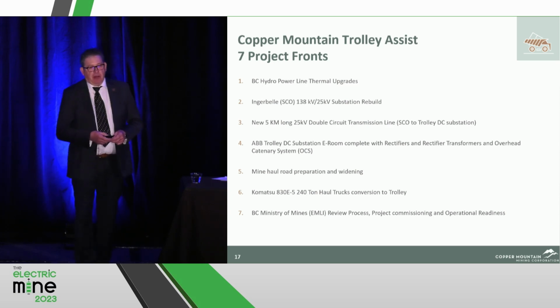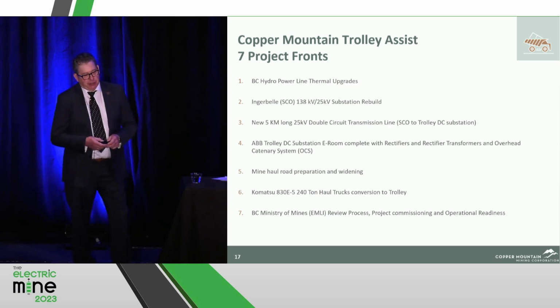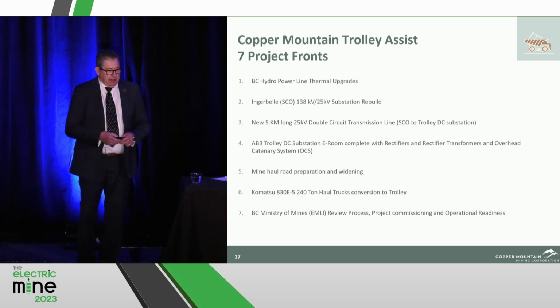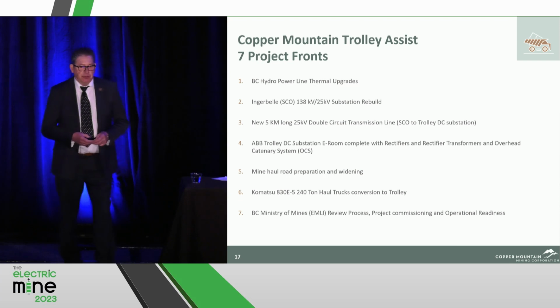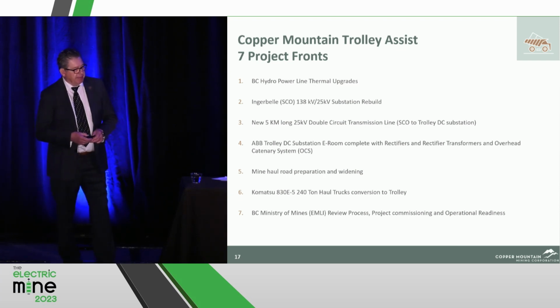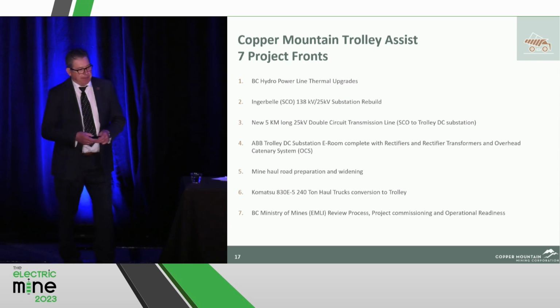We constructed 5 kilometers of 25 kV double circuit line from that new substation to the Trolley DC substation. And then with our partners, ABB, they delivered the E-room, modular E-room, complete with the 2 6-megawatt resi block rectifier transformers, and supplied the overhead catenary system.